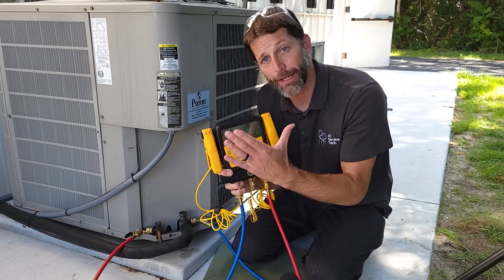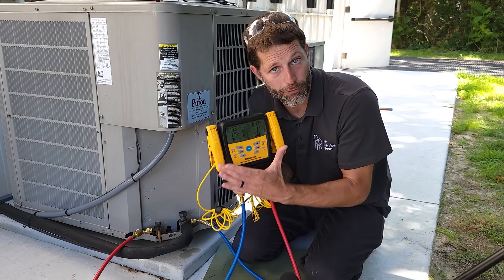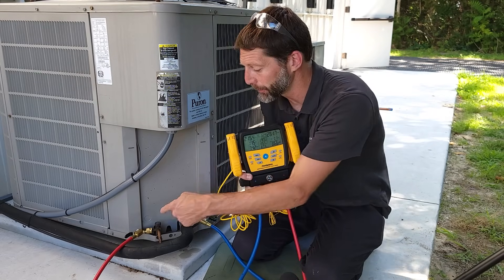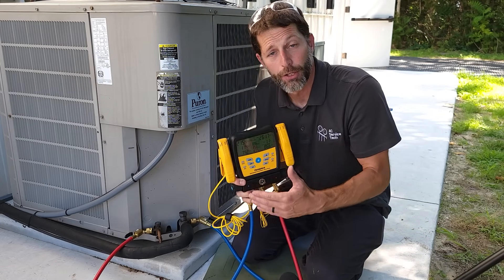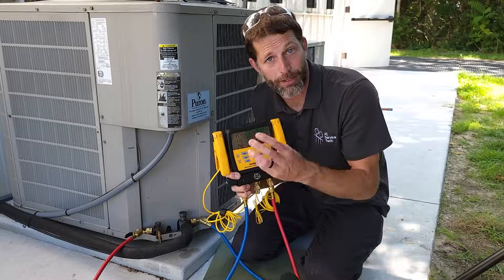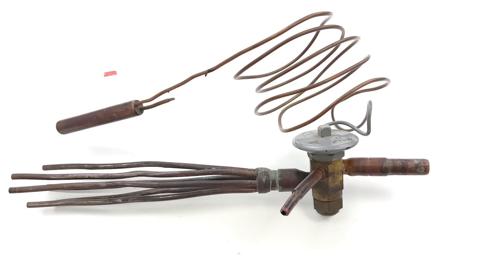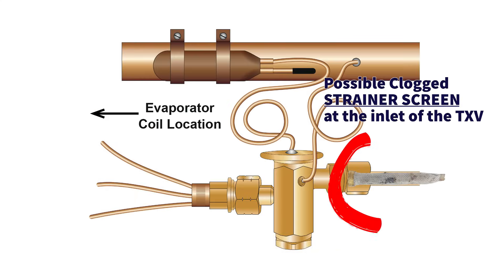We're also going to compare that against a liquid line restriction problem — that's a blockage in the liquid line. Maybe the TXV is bad and closed down, or the bulb has lost its refrigerant charge, which is the indoor metering device. You could also have a clogged strainer screen before the metering device, or a clogged filter dryer.